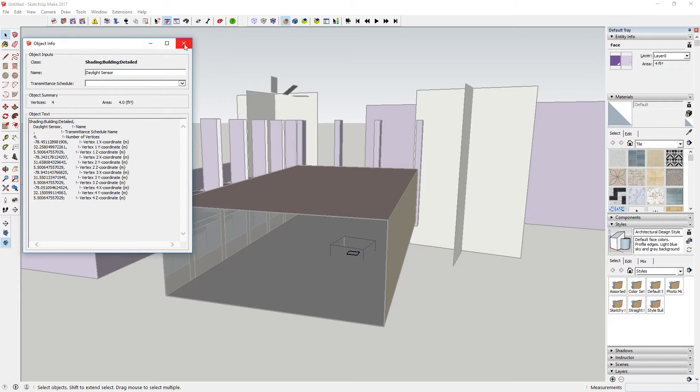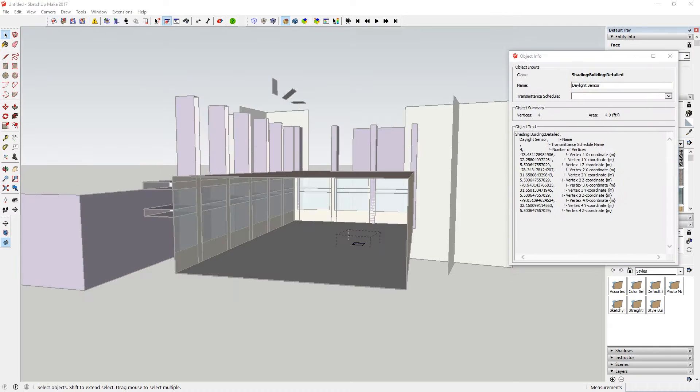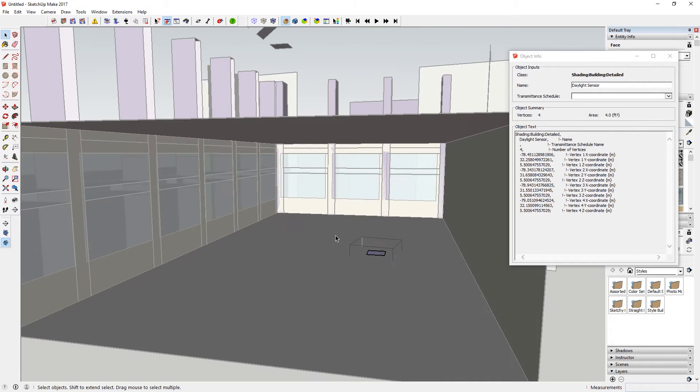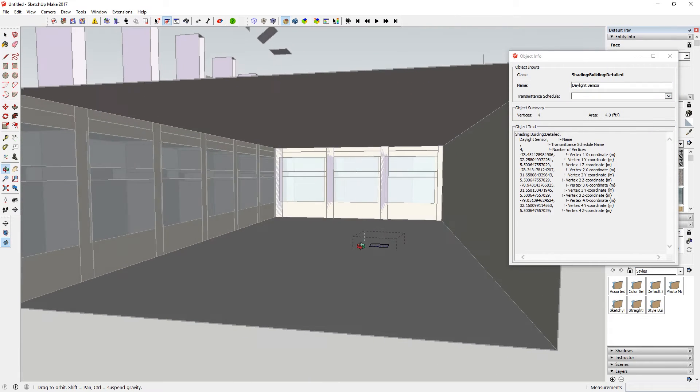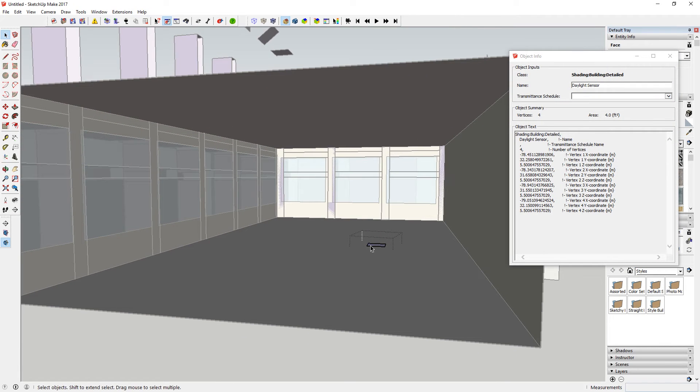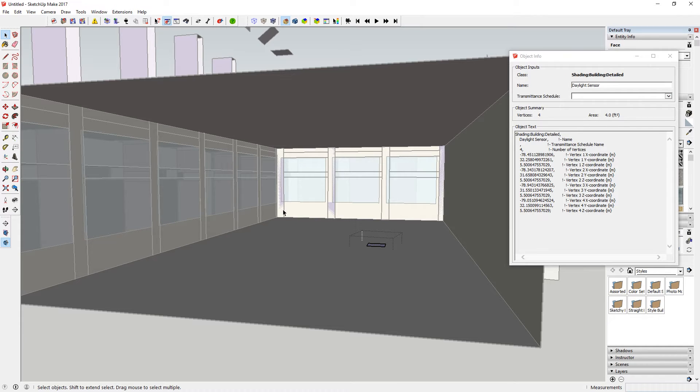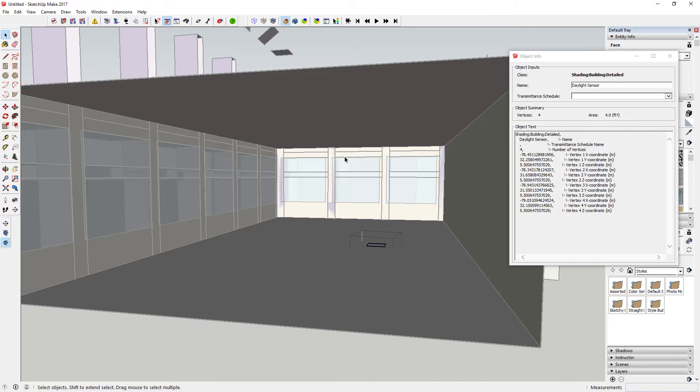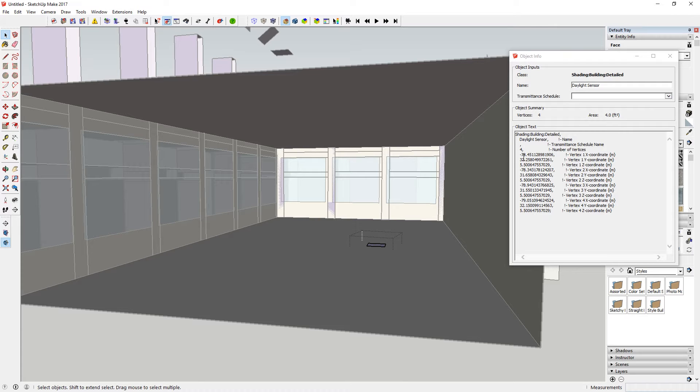So let me explain that. The purpose of a daylight sensor is to read the amount of light falling in a given area and to dim the electric lights accordingly. So if the electric lights are delivering 300 lux or 30 foot-candles, but that sensor sees that there's already 15 foot-candles or 150 lux, then it knows that they can dim those lights by 50% and get an equivalent of 300 lux.